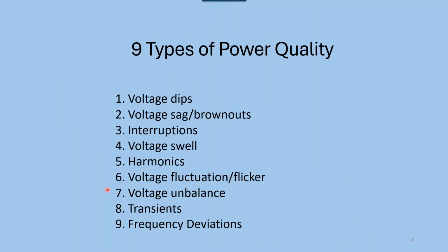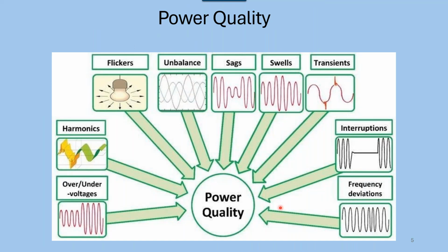So what is power quality? I've actually listed here 9 different types of power quality. It could be voltage dips, sags, brownouts, interruptions, swells. Harmonics is just one small part of power quality. Fluctuations or flicker, voltage unbalance, transients, and frequency deviations. I'm a visual guy, so I like to do it this way. Here's a picture showing over and under voltage. As you can see, if the voltage should have been somewhere in between these two, this is under, that's over voltage. Harmonics we'll cover in a lot more detail.